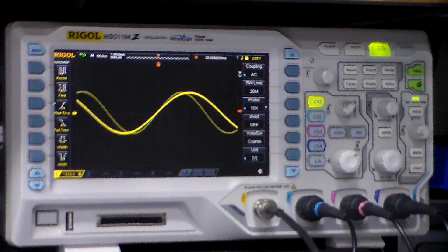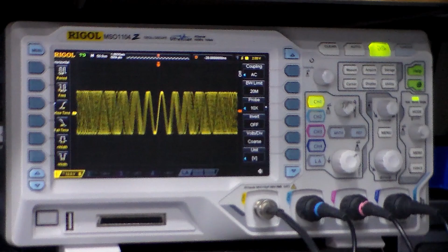Anyway, I'm going to put one of those in to replace the existing device, and that should fix our tracking generator problem, because we're not getting any signal out of the tracking generator, and it was traced to the output of this chip here in the A2 board. After installing the new chip, replacing the old U7, we've now got quite a decent output on the tracking generator, so that's at least resolved one of the issues in this device.